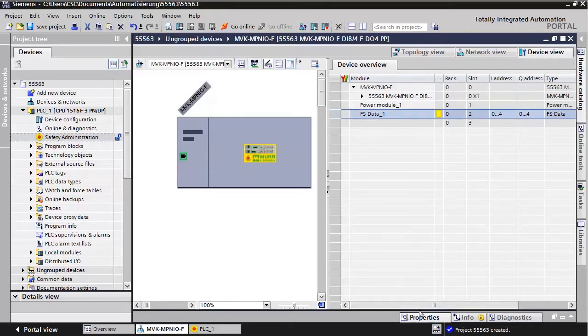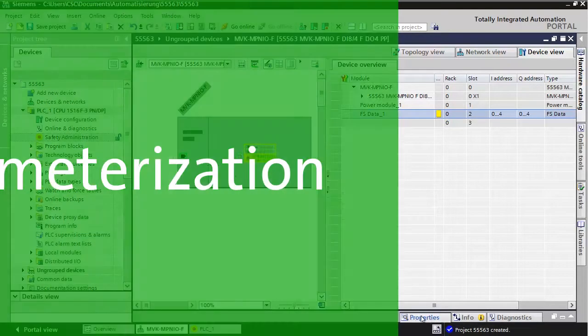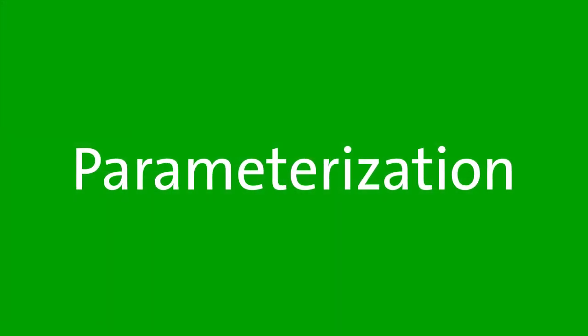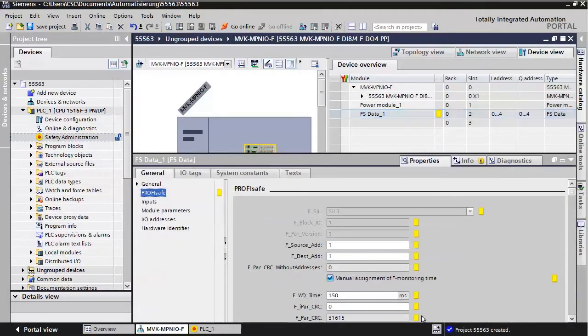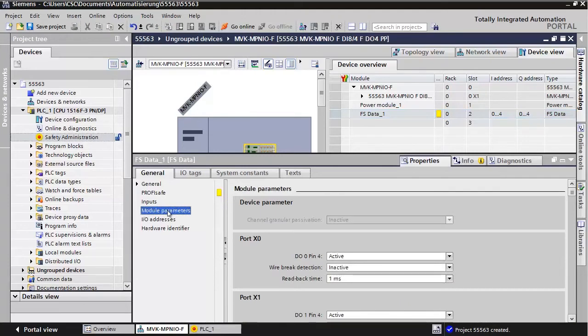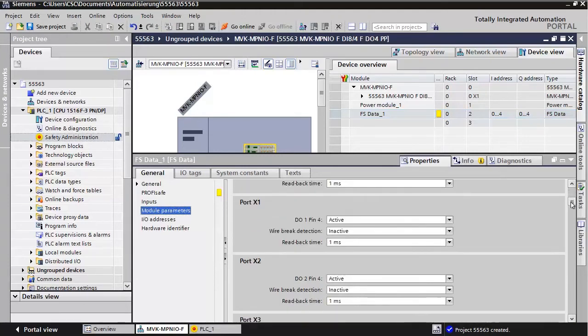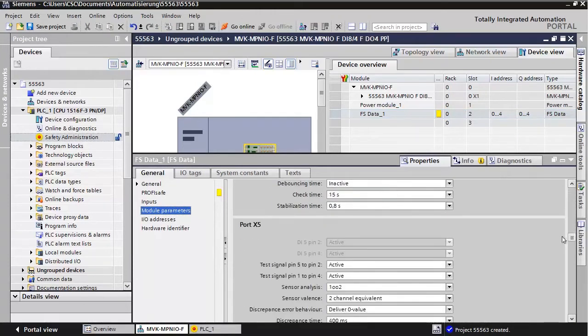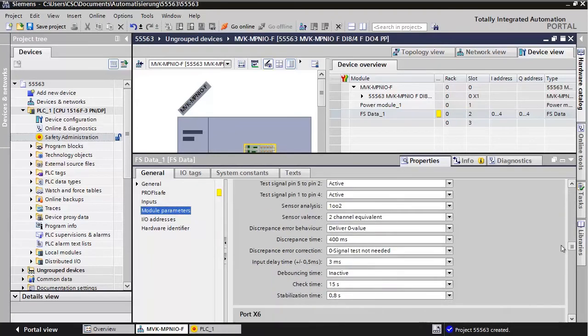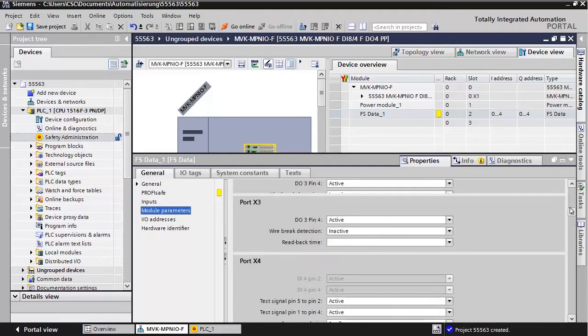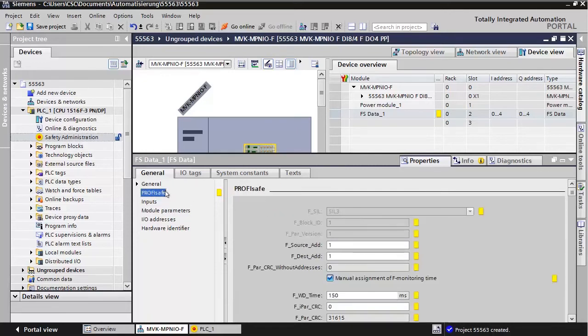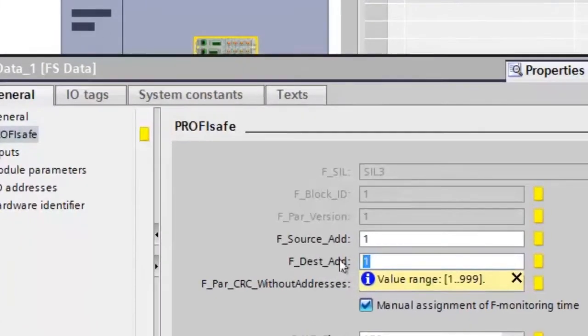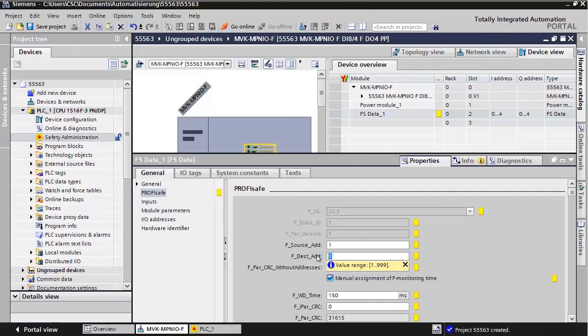Select it and go to its properties. In Module Parameters, you can define the parameters as you need. Under PROFISAFE, set the desired F Destination Address. You will need to set the same address on the module using the rotary switches.